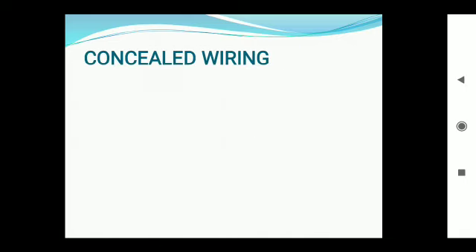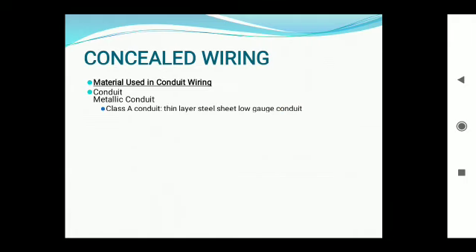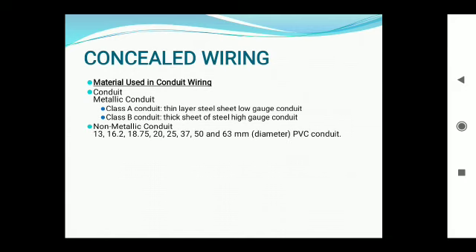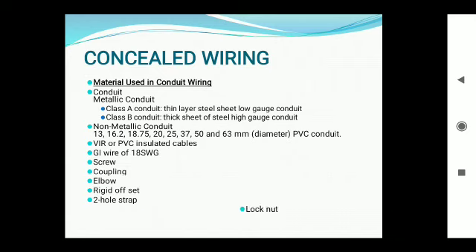Now the concealed wiring. The material used in concealed wiring is the same as the conduit wiring. So you can say the concealed wiring is concealed conduit wiring. Number one, the material used is the metallic conduit. And as with conduit wiring, there are two types of metallic conduit, class A and class B: thin layer steel sheet low gauge conduit and thick steel sheet. And here you can also use the non-metallic conduit as in conduit wiring. PVC cables, GI wire of 18 SWG or 14 SWG, screw, coupling, elbow, rigid offset, two-hole strap, lock nut.